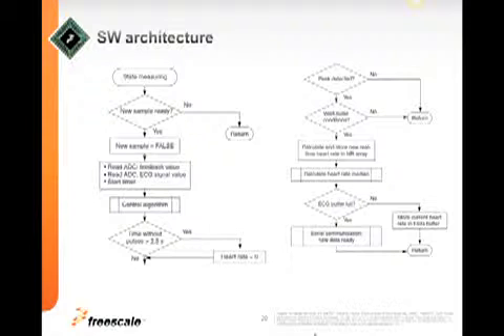If our current state is measuring, we check for new samples from the ADC. If there are new samples, then our new samples state will be false. We read the ADC, we read the ECG signal value, and we start a timer. Then we go to a control algorithm, and this control algorithm tells us if our time pulses is above 2.5 seconds. If a peak was detected, this means that a heartbeat happened. If it's a valid pulse, we calculate and store the new real-time heart rate in a heart rate array, and then we send all this data to a buffer for the ECG. If this ECG buffer is full, then we send this data through the USB with our serial communication new data ready.